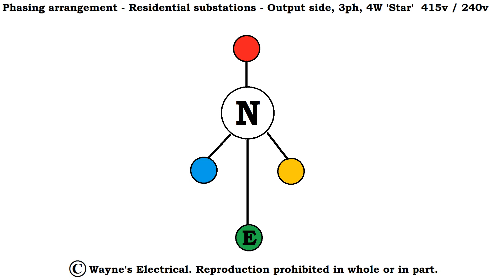So just to recap then, between any two phases, you get 415 volts, and between any phase and neutral, you get your 240 volts. Of course, that will vary. You do hear some people saying 400 volts and 230 volts, but as long as it's within the tolerances, it's roughly around about there.